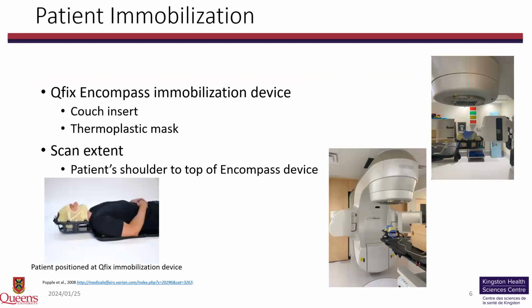So in terms of the patient immobilization device, for the treatment planning and delivery of the HyperArc plans, there's a specific immobilization device that needs to be used, and it is called the Qfix Encompass immobilization device, which consists of a couch insert and a thermoplastic mask that sits on the top, on the raised component of the couch insert. And it is recommended by the vendor that we should scan the patient from shoulder to the top of the Encompass immobilization device to make sure that the entire anatomy is captured during the CT sim.